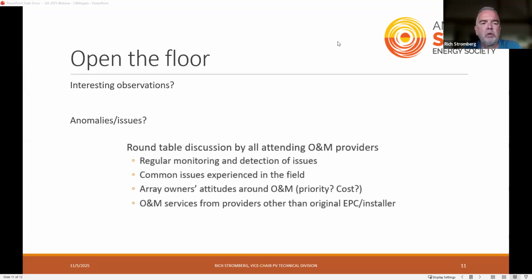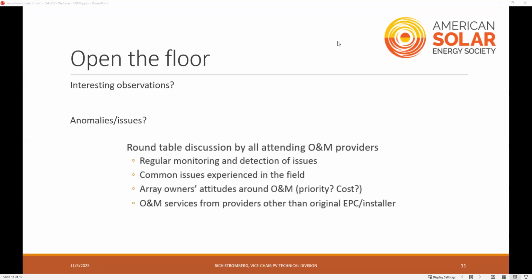Drew, another thing too on your system, smaller systems, microinverters and DC optimizers are fine. There is a pretty sizable group of installers and O&M providers that, and I tend to agree with them, that the larger your system, you want to get away from module level electronics, because both the module and the optimizer or microinverter, those are both failure points. All of the connectors are failure points. And you do have a higher probability of issues to respond to, and rooftop fires as well.